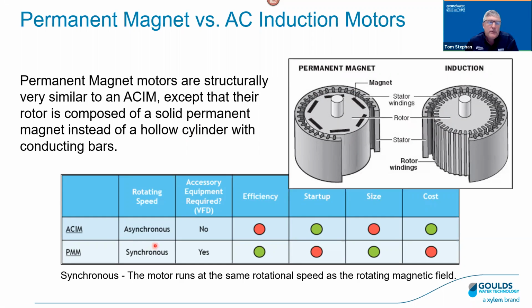So here are some things to think about in terms of the differences here on the bottom. Again, ACIM, AC induction motor. The one big difference is that it is an asynchronous motor. There is what we call slip in that motor. And basically that is where the motor does not run at the same rotational speed as the rotating magnetic field. Whereas the permanent magnet motor, that's a synchronous motor. And synchronous is the motor does run at the same rotational speed as the rotating magnet. So that's one key difference.